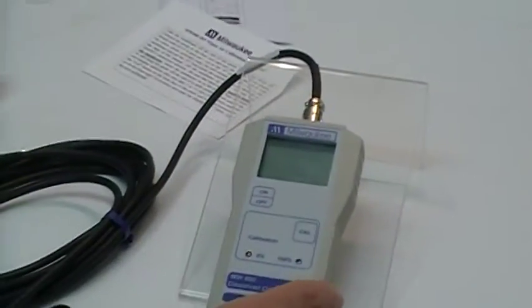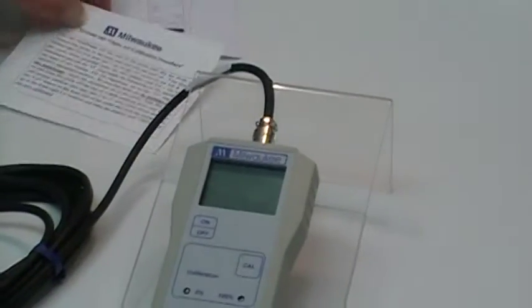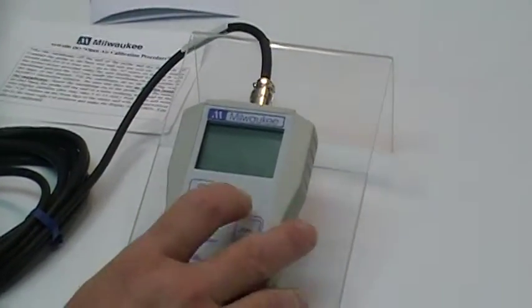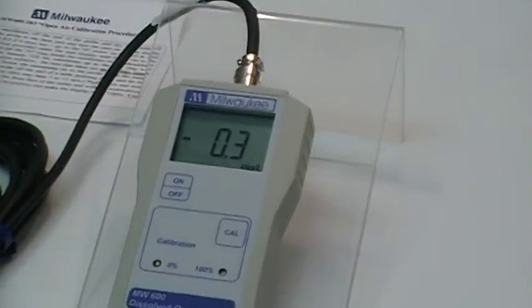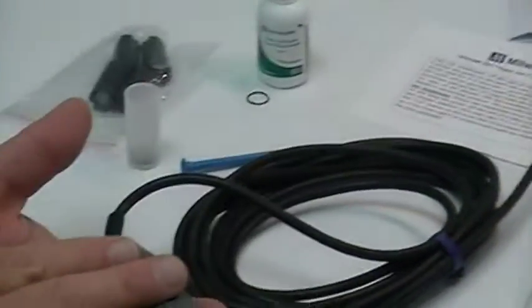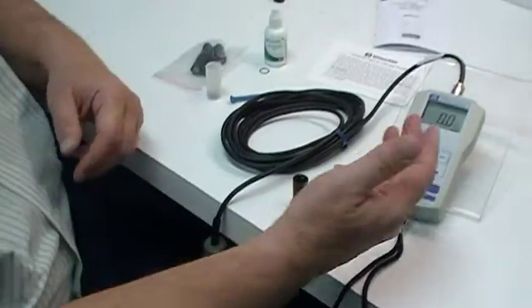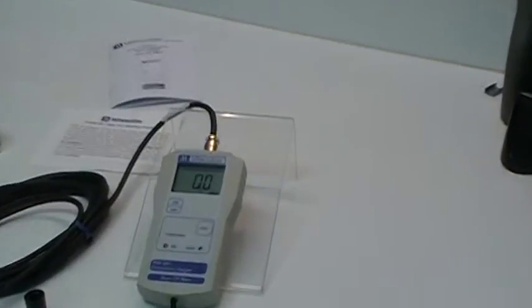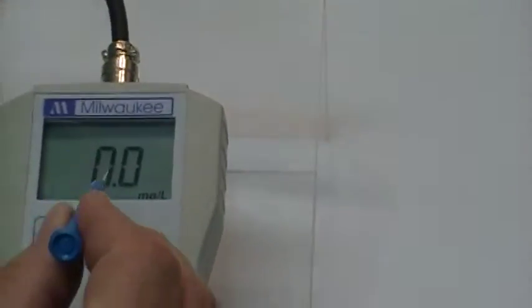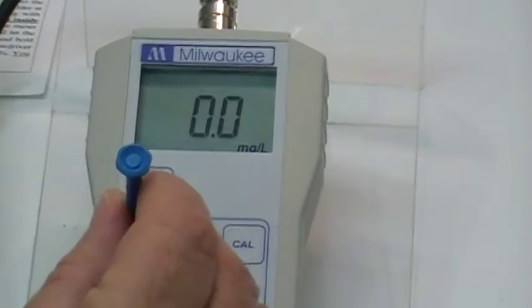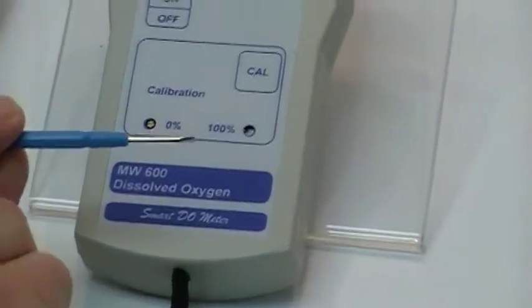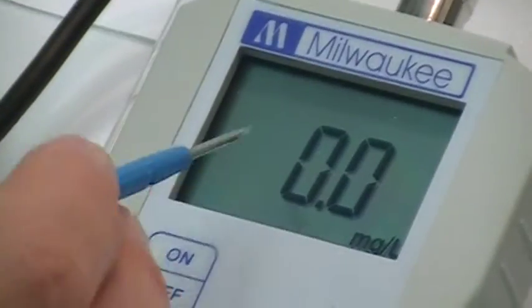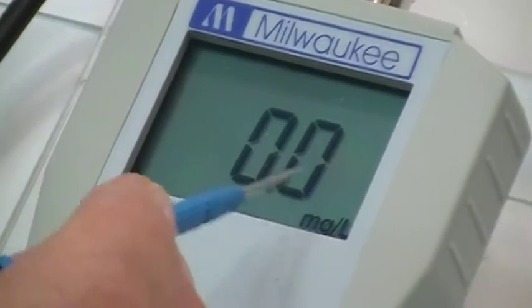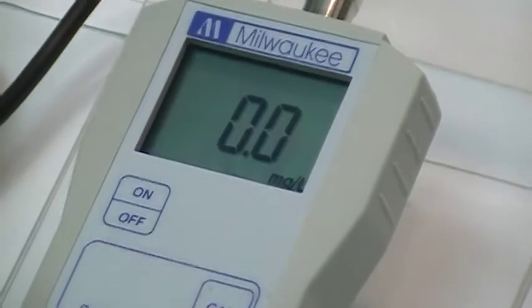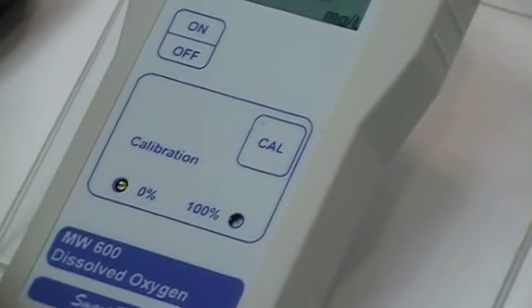At this point, according to the open air calibration procedure, you're going to turn your unit on with your probe and an exposed diode, no membrane. You should see a 0.0 come up on your screen. If you do not, go to the 0 with your provided screwdriver and dial it in to where you do see 0.0, not a negative or any other figure. This is what you want to start off with, to zero the unit.